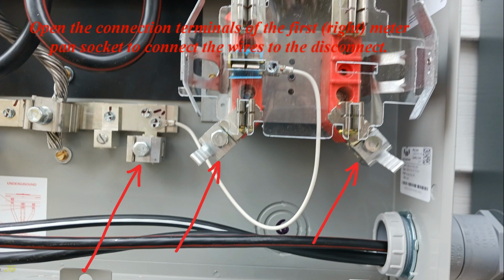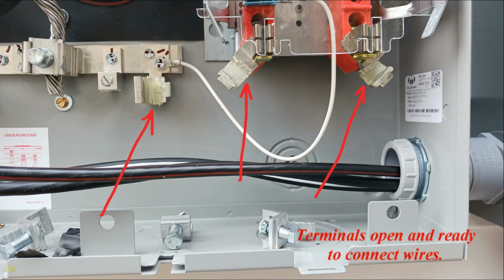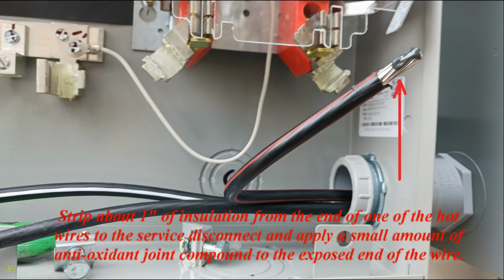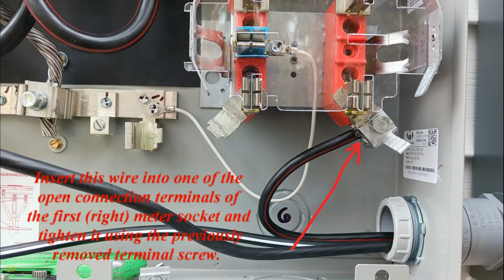Open the connection terminals of the first, right, meter pan socket to connect the wires to the disconnect. Terminals open and ready to connect wires. Strip about 1 inch of insulation from the end of one of the hot wires to the service disconnect and apply a small amount of antioxidant joint compound to the exposed end of the wire. Insert this wire into one of the open connection terminals of the first, right, meter socket and tighten it using the previously removed terminal screw.